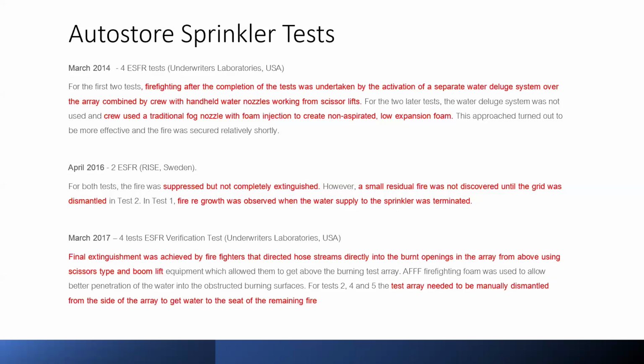And then we went off to Underwriters again. Final extinguishment was achieved by firefighters that directed hose streams directly into the burnt openings of the array from above using scissor lift type and boom lifts. So they're not available on these systems. Test array needed to be manually dismantled from the side of the array to get water to the seat of the remaining fire. So now they're taking it to bits and burrowing their way in.